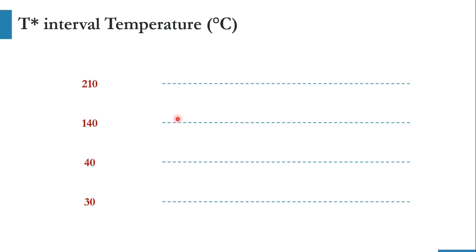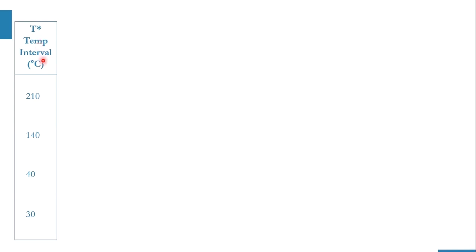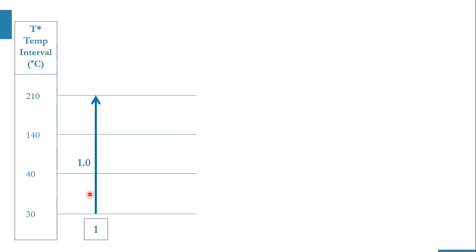There are three intervals: 210 to 140, 140 to 40, and 40 to 30°C. The cold stream (labeled blue) goes from 30°C to 210°C, and the hot stream goes from 140°C to 40°C. Now for the T* temperature intervals — 210, 140, 40, 30 — stream one (cold) has CP value of 1, and the hot stream has CP of minus 1.8, since in the formula it appears as CP of C minus CP of H.